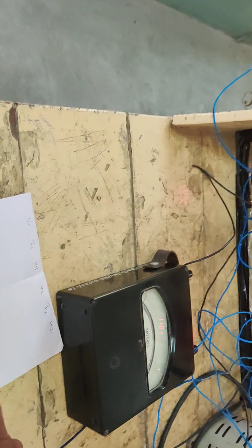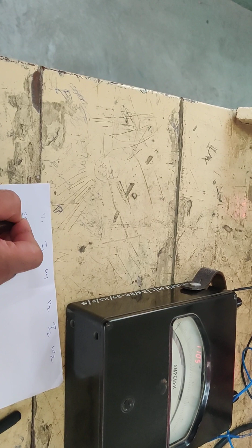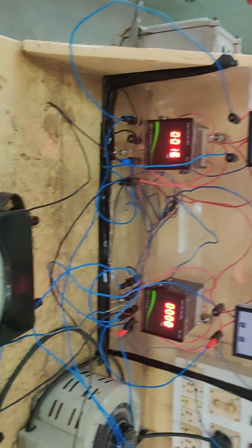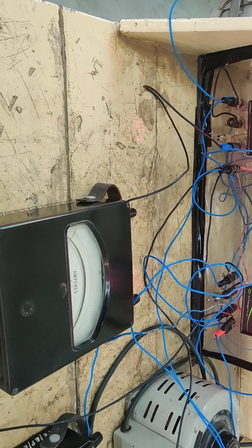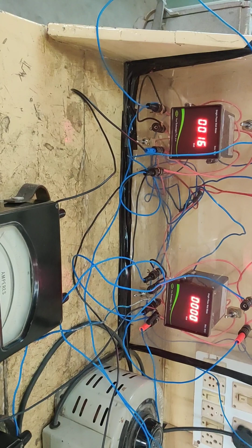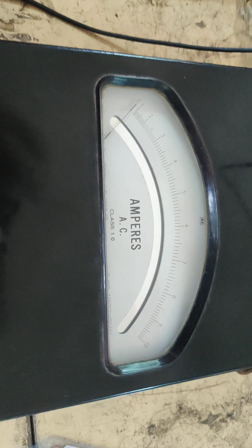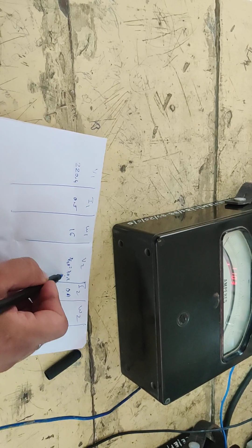Now this V1 is 220 volts, 220.4. Then I1 here is 0.5. Then W1 here is 16. V2 no load voltage, we may call this the no load secondary side voltage, V2 0 is equal to 110.2. Then I2, see here, I2 is 0 ampere. So here it is 0 ampere. By multiplying these two we have 0 watt. Similarly on the secondary side we have 0 watt.